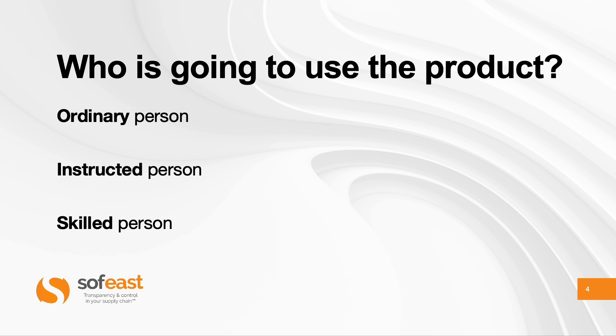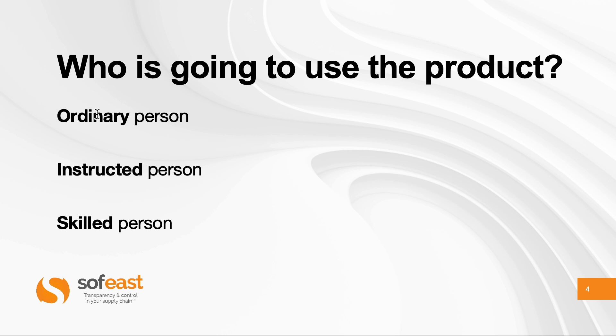Another concept: who is going to use the product? An ordinary person, an instructed person, or a skilled person — this is a very important concept. A skilled person is someone who knows very clearly what the hazards are and has significant experience in how to avoid them. An instructed person has been trained by a skilled person — not just reading a user manual, but actual training or supervision. An ordinary person is everybody else.